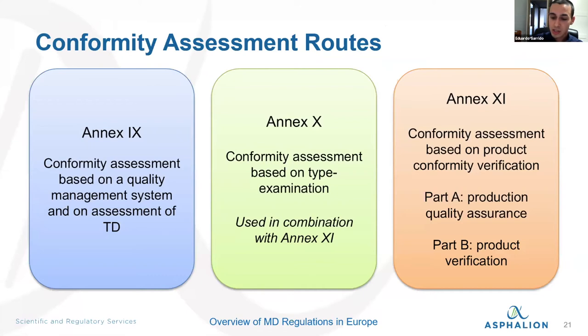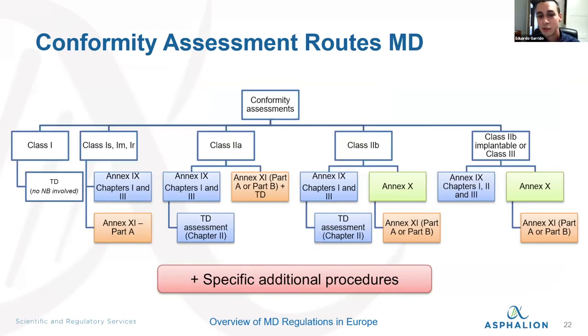Once you've identified all these requirements and gathered the technical documentation, you have to undergo a conformity assessment route. There are three assessment routes identified in the regulation, and depending on the class of your device, you will follow one or another. For instance, if you're class one, you only have to compile your technical documentation — there is no conformity assessment. But if you're class 2B, you have to follow either Annex 9 or Annex 10 — you have to check the regulation to see which one applies. You have a summary here in this slide.